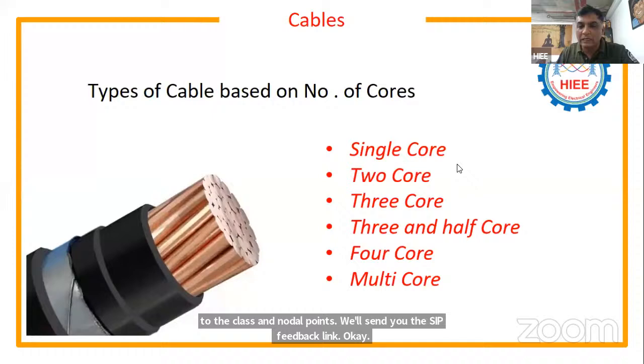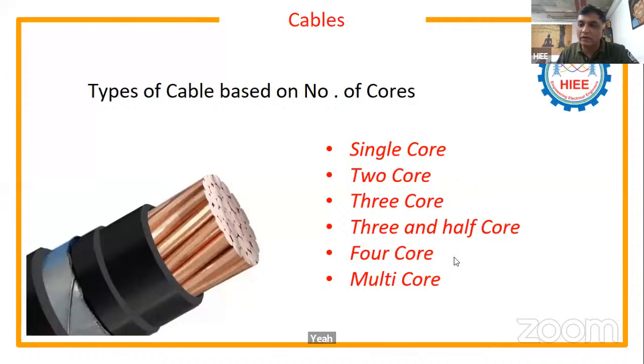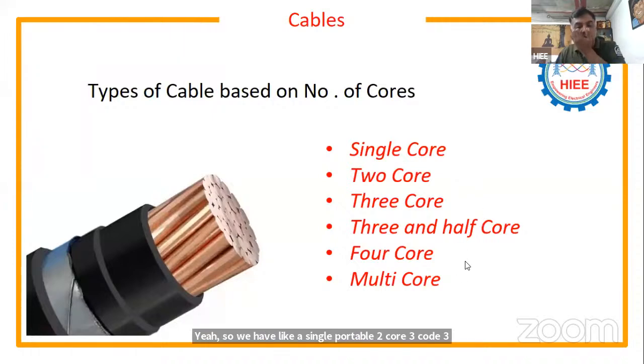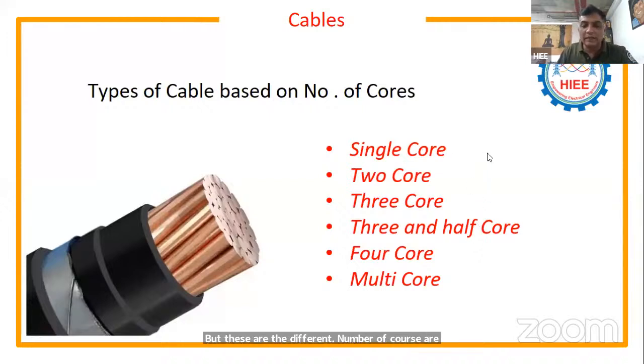So we have a single core cable, 2-core, 3-core, 3.5 core, 4-core, and multi-core cable. These are the different numbers of cores available. Now we need to understand the application: where we use single core cables, where we use 2-core cables, and for which application we use 3-core, 3.5 core, 4-core, and multi-core. Mostly multi-core cables are used as control cables, and single core, 2-core, 3-core, 3.5 core, and 4-core are used as power cables.